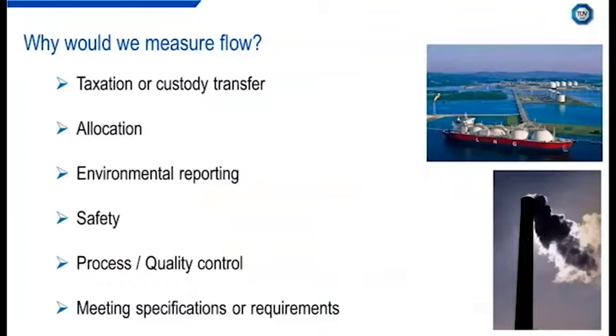Flow measurement is vital for taxation, custody transfer and allocation in the trade of oil and gas. Oil and gas being lucrative commodities, accurate flow measurement is important, with more focus on achieving lower measurement uncertainty within the oil and gas industry. Across many industrial sectors, there are safety and environmental regulations which exist, making flow measurement necessary to ensure specifications or requirements are being met.